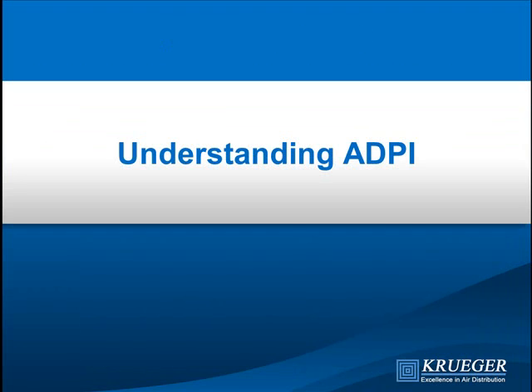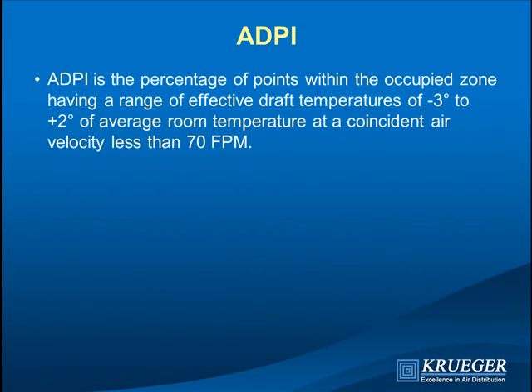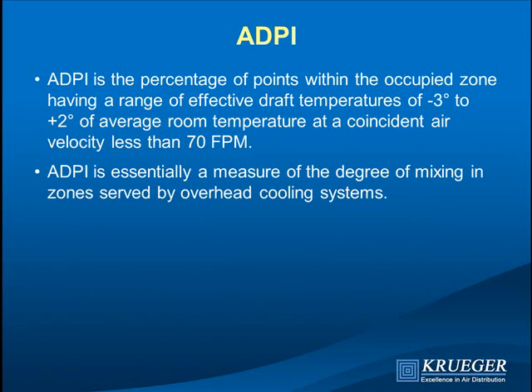ADPI — Air Diffusion Performance Index — is a means of predicting and reporting temperature and velocity spread within the occupied zone. It is the percentage of points that have a calculated draft temperature between minus three and plus two degrees, which are the boundaries of comfort for a person at one met and one clo at about 75°F. Points with air velocity above 70 feet per minute are excluded. ADPI is a measure of the degree of mixing in zones served by an overhead system.